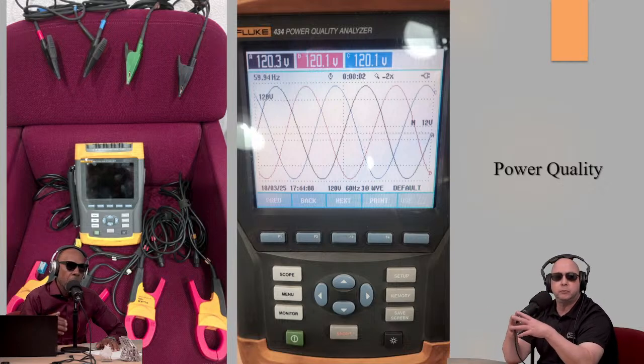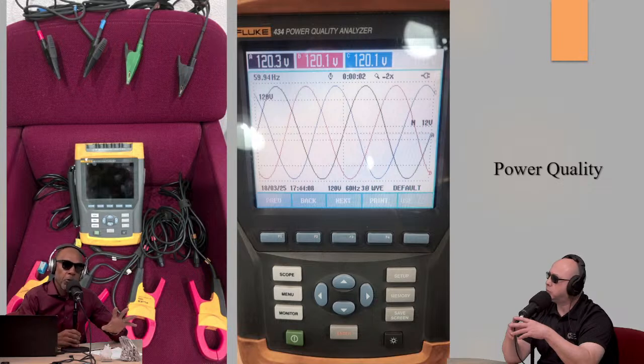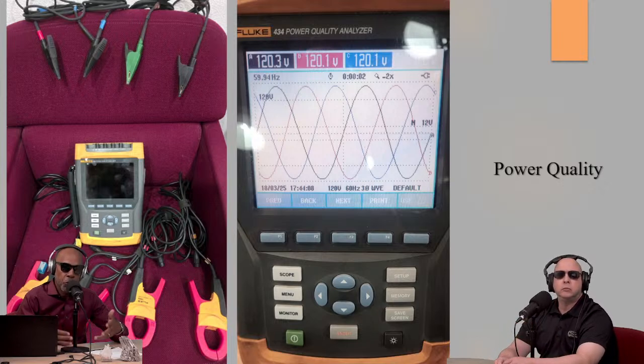In both of these scenarios, the clips and the clamps are on the output of the UPS, not on the input, because we're not really concerned about the source power. You can look at the source power coming into the UPS, but we're really concerned about the cleanliness of the power going to the devices, the critical load, the servers, that type of thing. That's what we're measuring here.